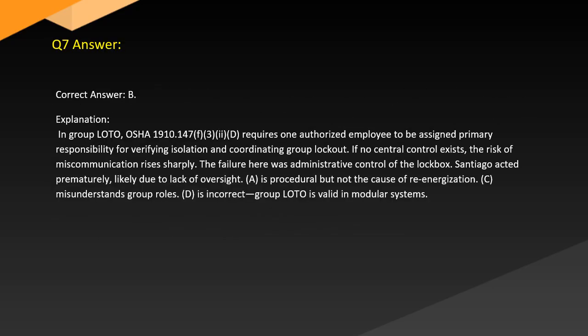Answer. Correct answer: B. Explanation. In group LOTO, OSHA 1910.147(f)(3) requires one authorized employee to be assigned primary responsibility for verifying isolation and coordinating group lockout. If no central control exists, the risk of miscommunication rises sharply. The failure here was administrative control of the lockbox. Santiago acted prematurely, likely due to oversight. A is procedural but not the cause of re-energization. C misunderstands group roles. D is incorrect. Group LOTO is valid in modular systems.